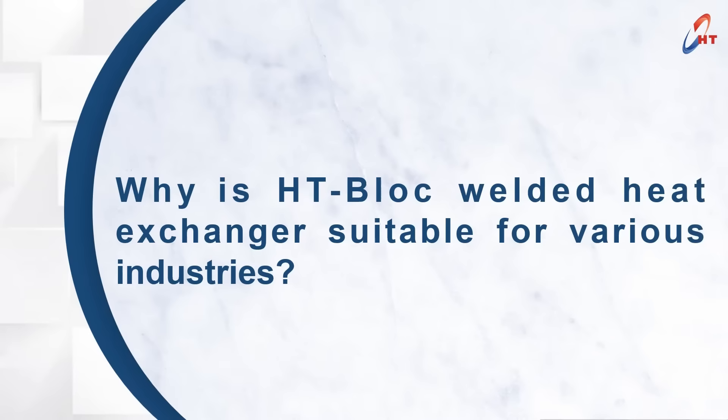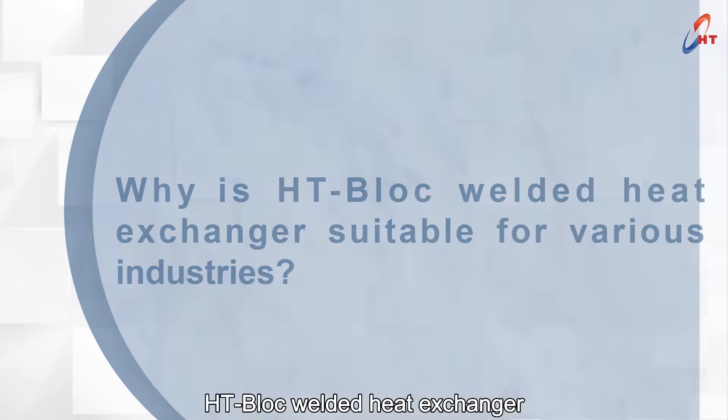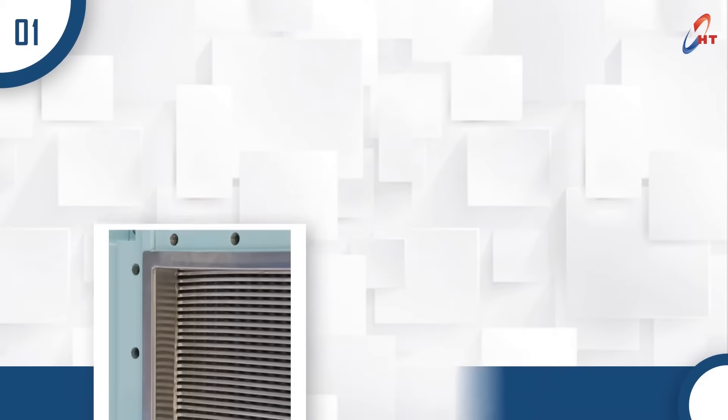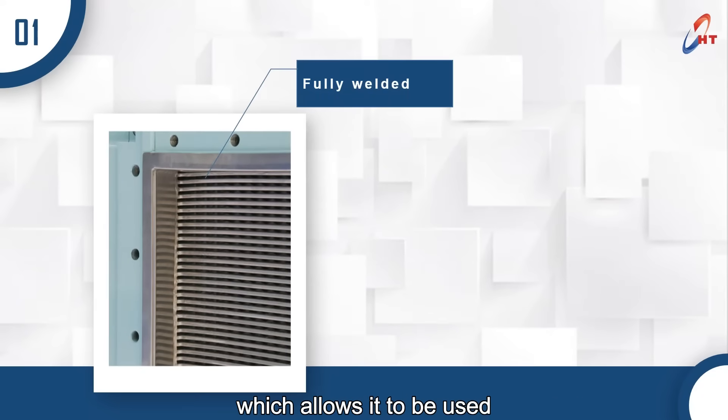Why is the HT-Bloc welded heat exchanger suitable for various industries? The reason lies in a range of advantages. First of all, the plate pack is fully welded without gasket, which allows it to be used in processes with high pressure and high temperature.